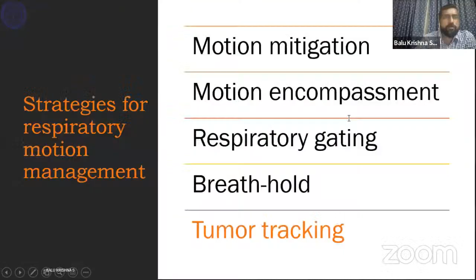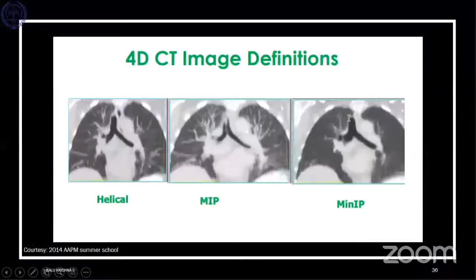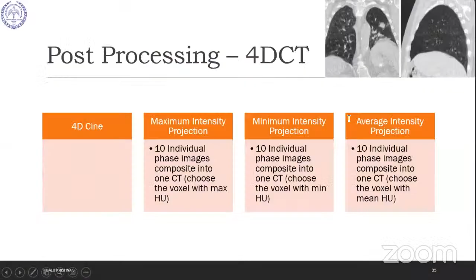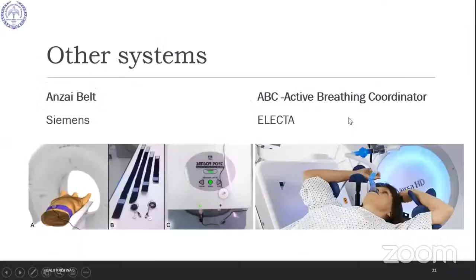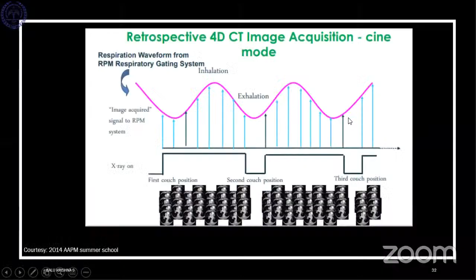Okay, binning. So this is phase binning. Phase binning is what we generally employ, where you divide the respiratory cycle into 10 phases. Every couch position, the scanner has acquired 10 images, one for each. So you have, let's say, 100 couch positions in one pass. You have 100 into 10 slices now.